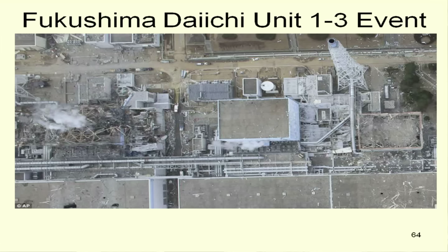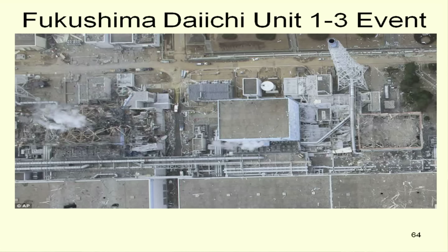In the course of trying to keep these reactors cool, the Japanese operators started circulating seawater through them, which means the reactors are shot, even if they weren't before, but they made a deliberate decision to do that. I've seen some anecdotal accounts that maybe they waited a bit too long to do that. But again, they were having troubles with instrumentation and figuring out where the water level was. Is the core uncovered or not? So that was the situation in Units 1, 2, and 3.